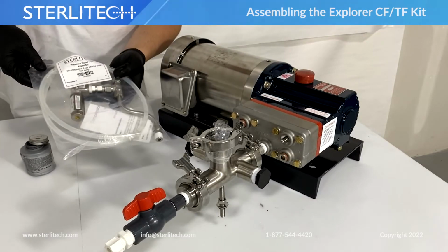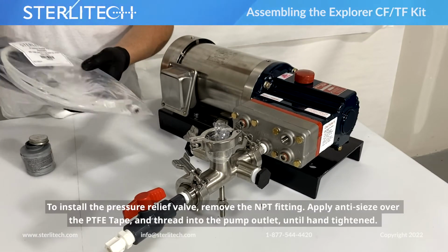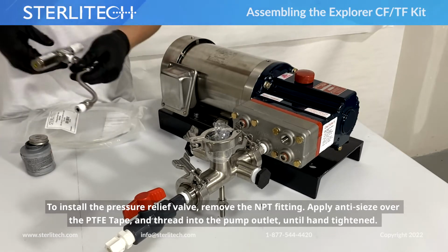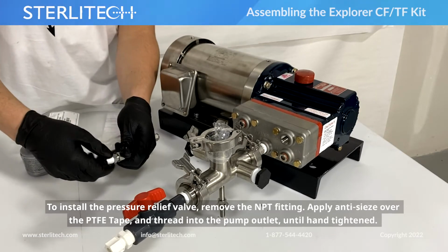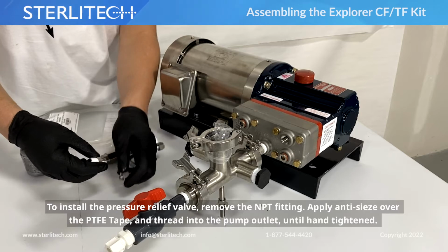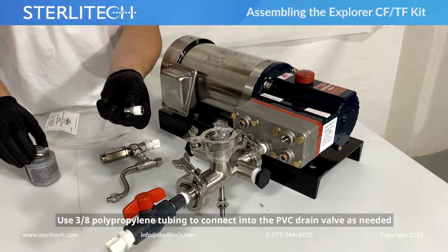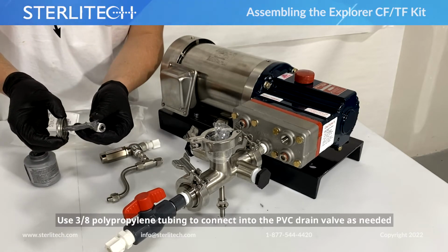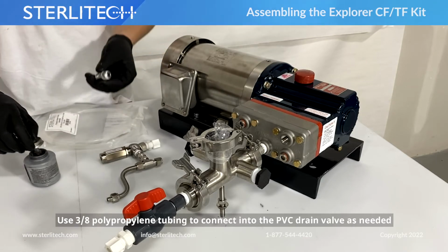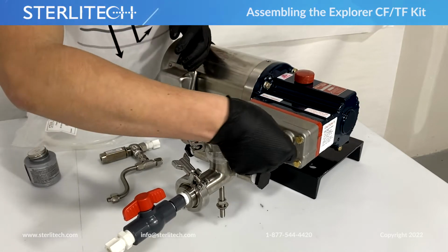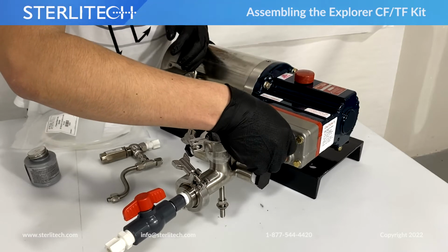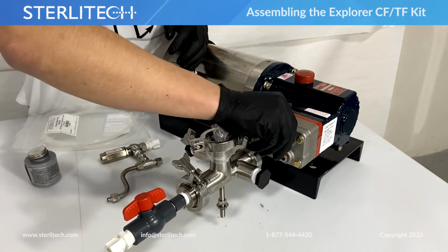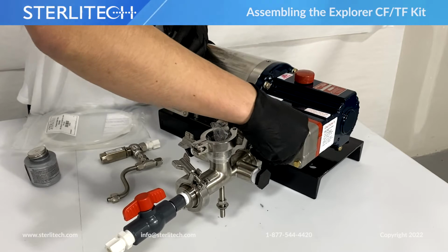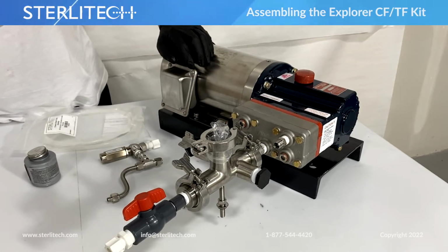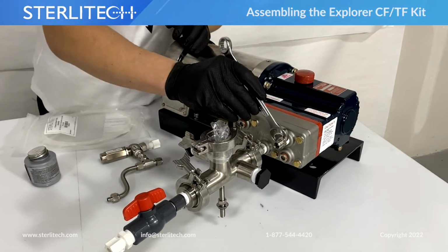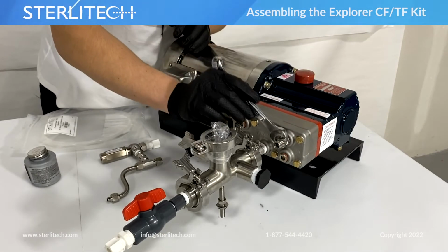Up next, we'll be installing a pressure relief valve. What I'm going to do is remove this MPT fitting on the one side. It's got PTFE tape already applied. We're just going to add another bit of anti-seize. We're going to thread that into the upper right port on your pump head.